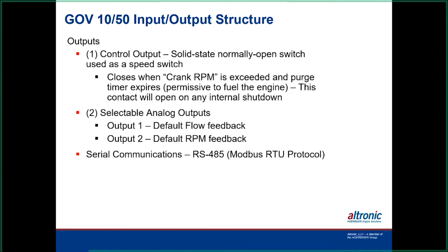Control outputs on it. It will close when the cranking RPM is exceeded and purge timers expire. And this allows you to open up a switch to turn the fuel on from the block and bleed to get fuel flowing through this valve. So it's, again, a very important part of the purging and to help calibrate the valve.